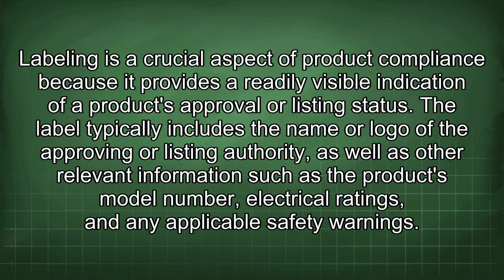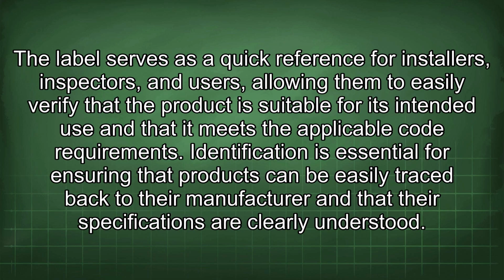Labeling is a crucial aspect of product compliance because it provides a readily visible indication of a product's approval or listing status. The label typically includes the name or logo of the approving or listing authority, as well as other relevant information such as the product's model number, electrical ratings, and any applicable safety warnings. The label serves as a quick reference for installers, inspectors, and users, allowing them to easily verify that the product is suitable for its intended use and that it meets the applicable code requirements.